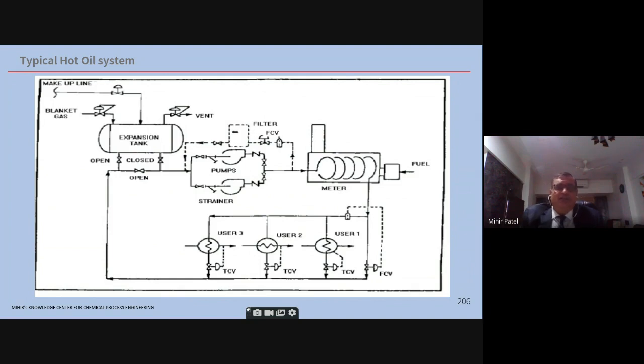Dowtherm is a thermic fluid in vapor condition. There is a Dowtherm fluid vaporizer, electrically operated, at the ground floor. The vapor rises up like steam, condenses on the melt line, and comes back into the Dowtherm vaporizer. Dowtherm A is used for nylon 66. It starts boiling at 257 degrees centigrade and creates only 0.3 bar gauge pressure at around 290 to 295 degrees centigrade. Dowtherm J is used for polypropylene because it starts boiling at around 180 degrees, and at around 195 it again creates about 0.3 bar.